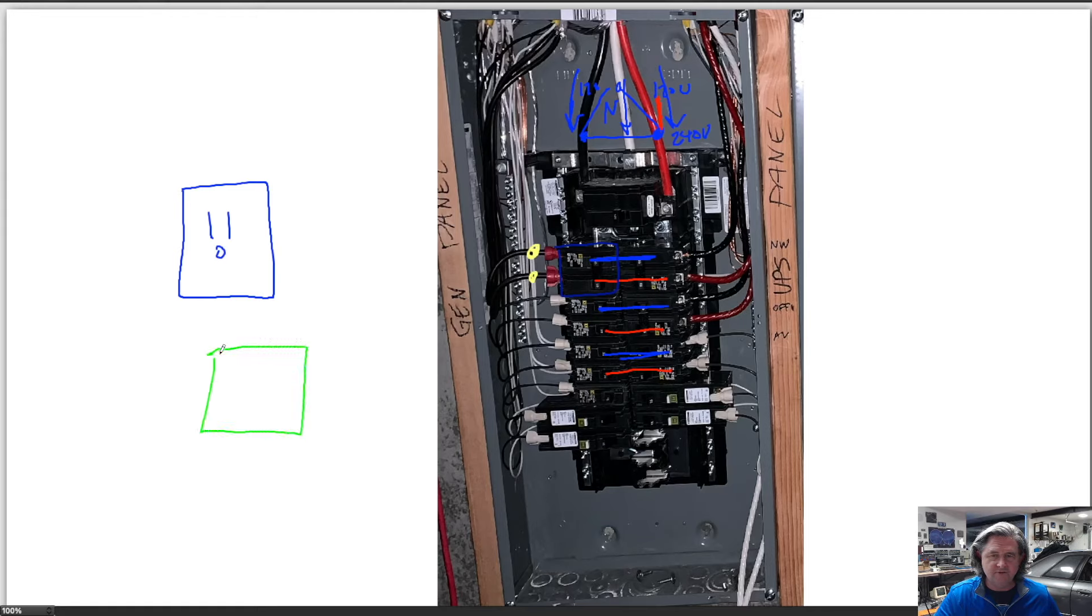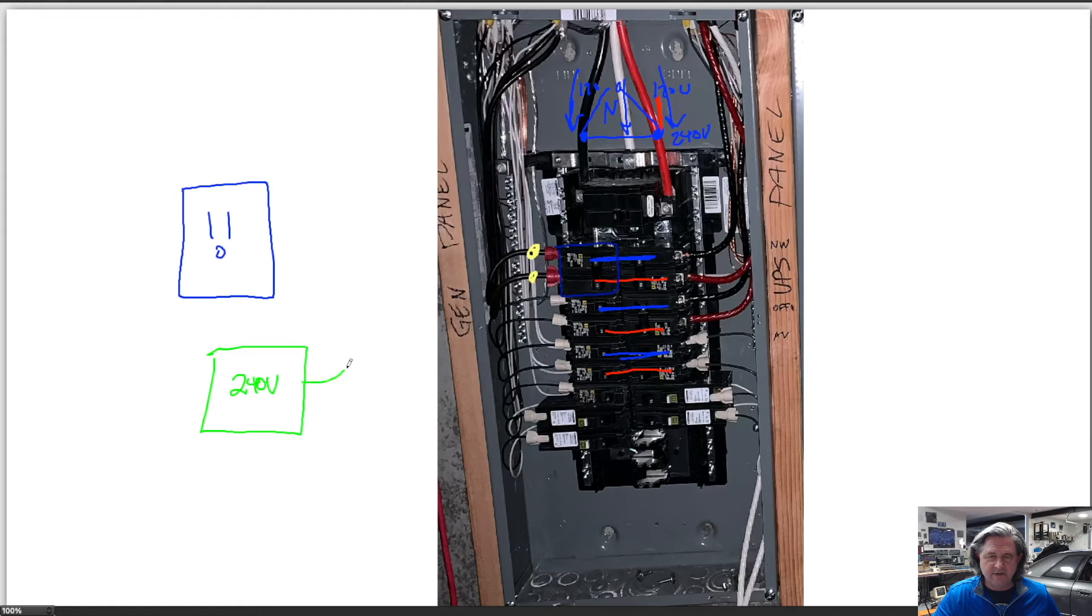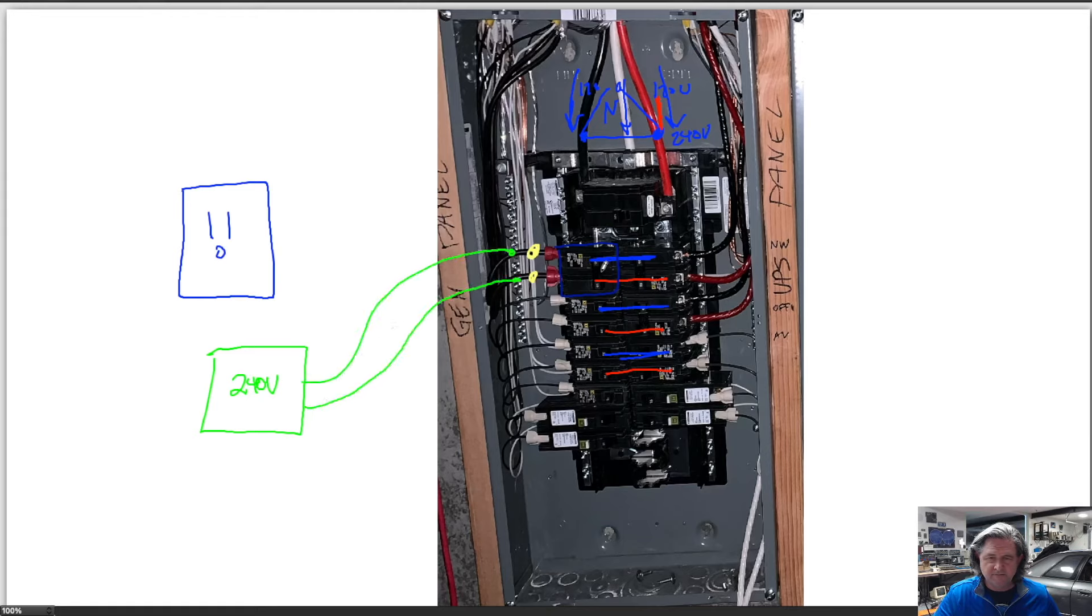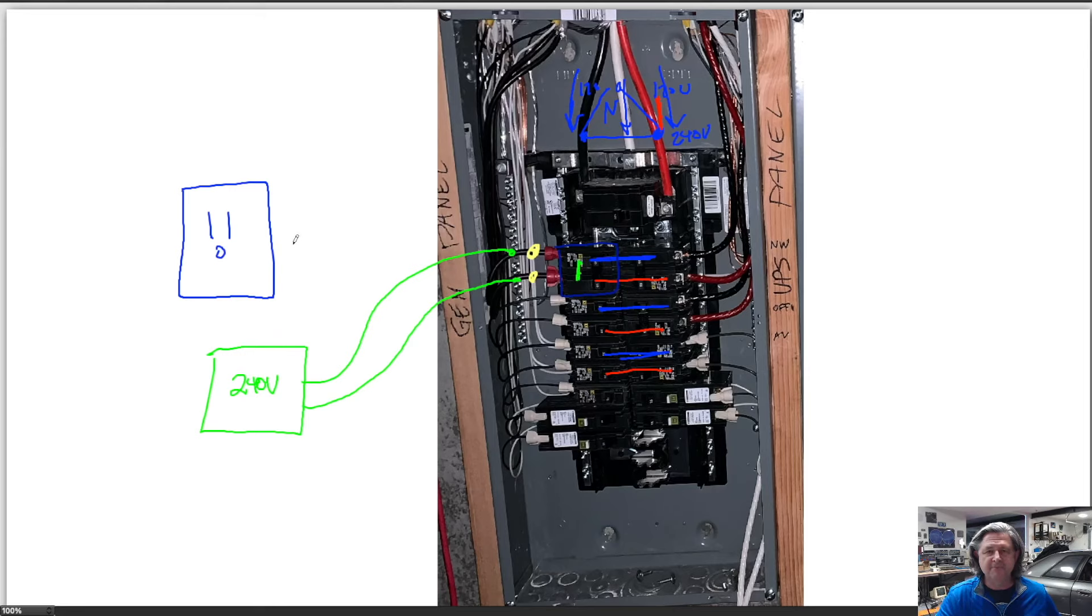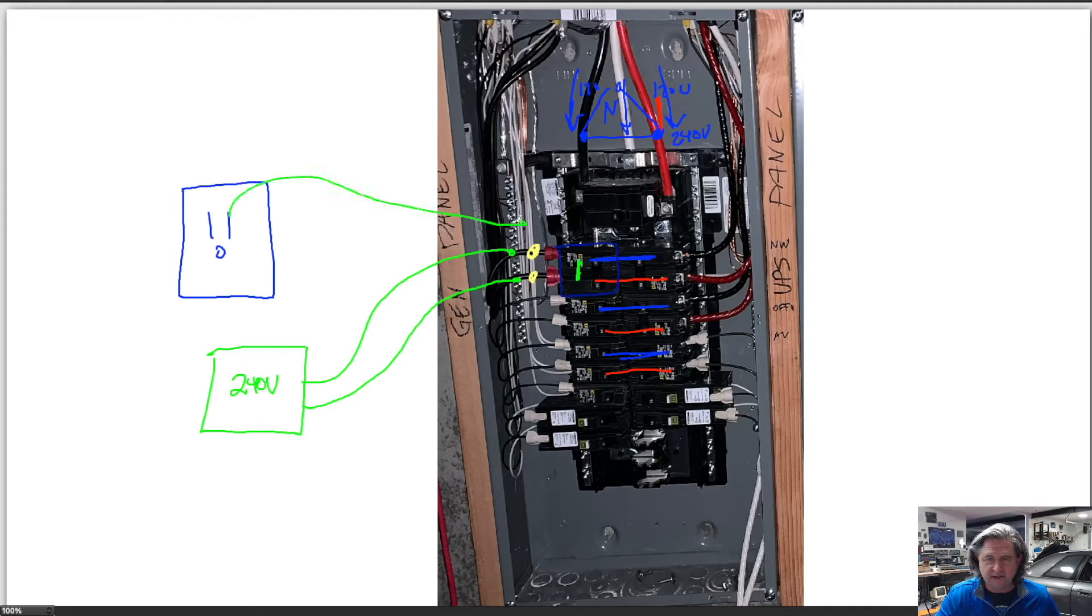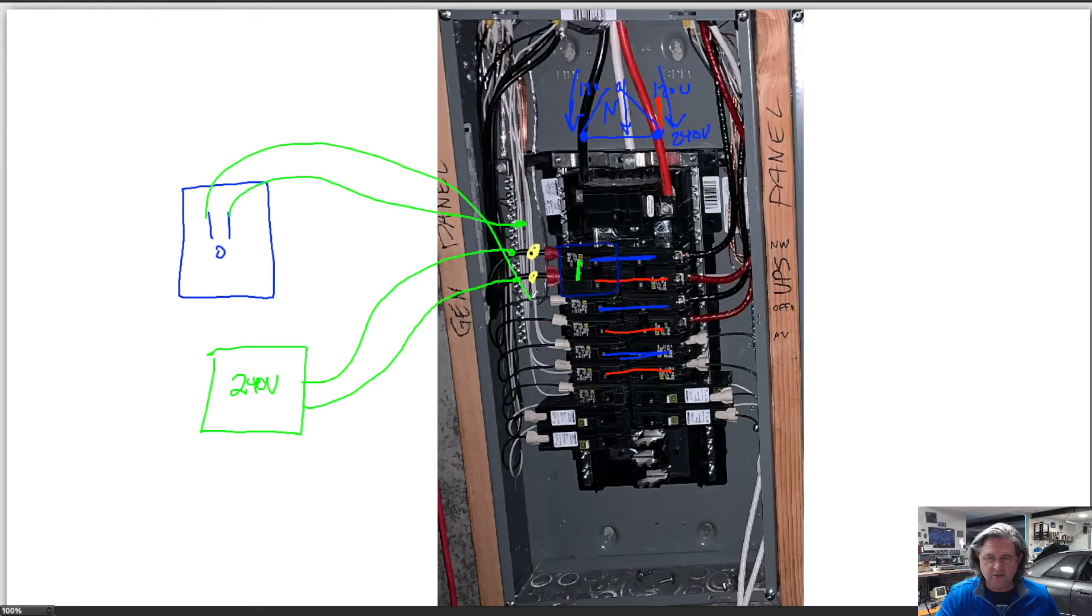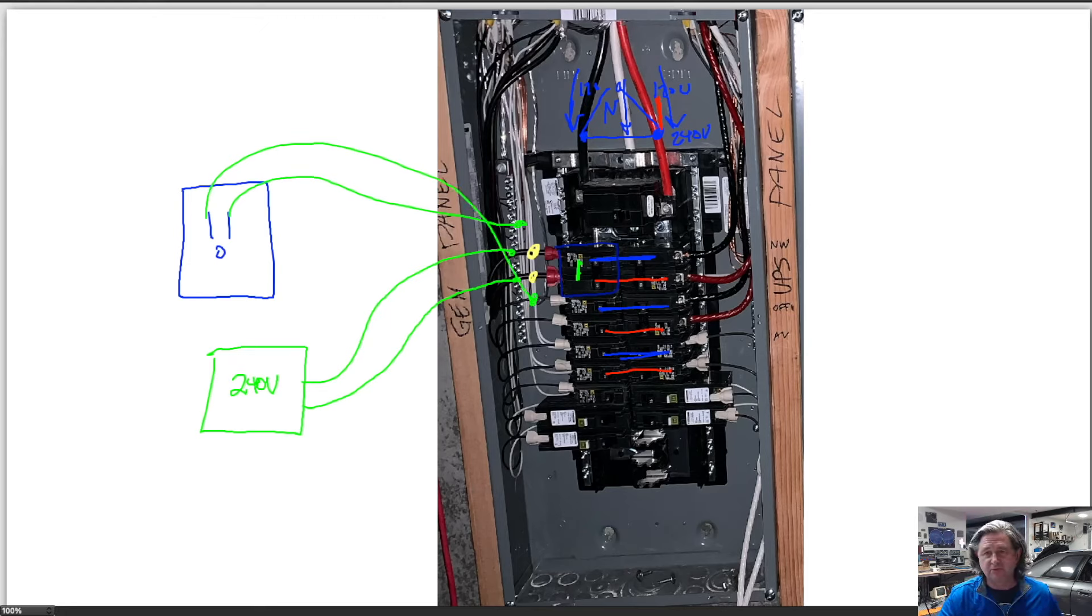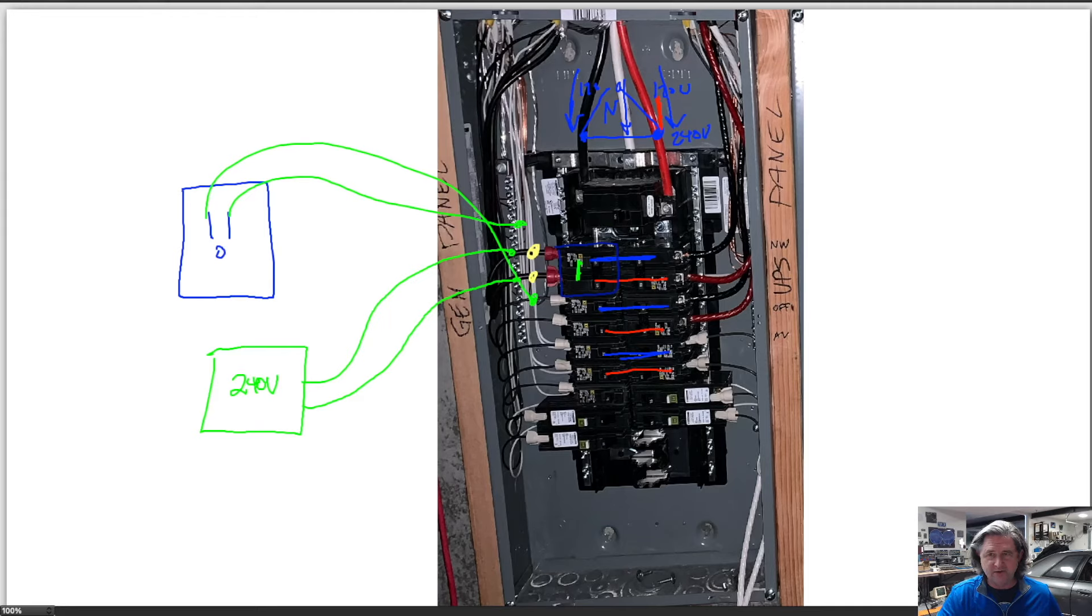So if you have a dryer over here and your dryer is a 240 volt dryer, those two wires will be connected each one to a different part of that sort of paralleled breaker and that gives you 240 volts. Meanwhile a 120 plug would have one wire going to the neutral and the other wire going to just one of the breakers.